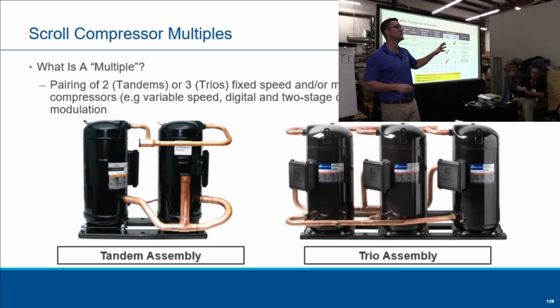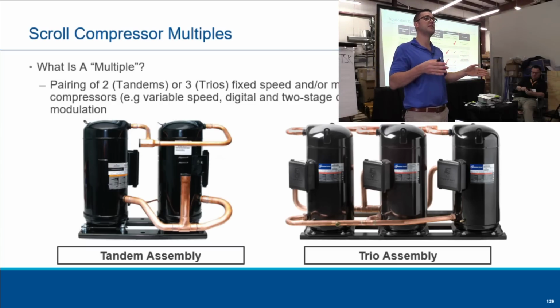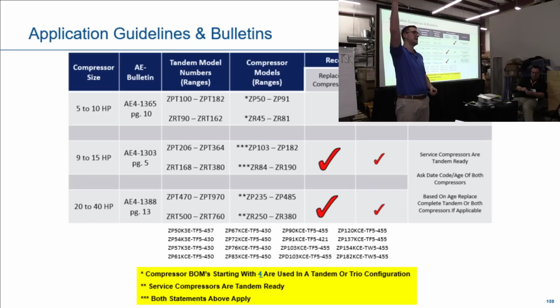The biggest question from contractors: do I have to replace the tandem set, or can I just replace one? How many people say you always have to replace the tandem set? Show of hands. So three or four people. No, that's not the case. It all depends on the model of the compressor. It depends on whether we have a service model. If we don't have a service replacement, you're going to have to replace the tandem. Once again, get into the AE bulletins.